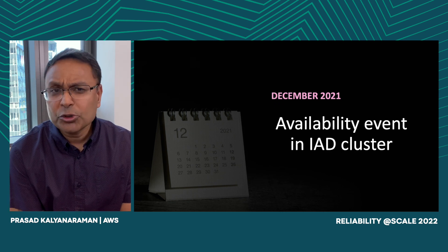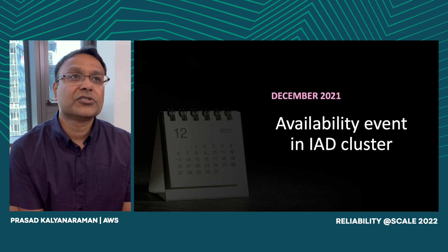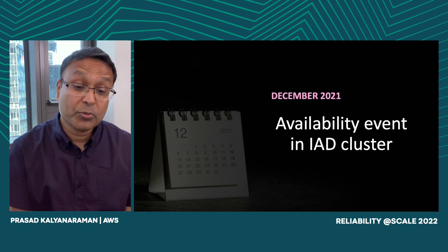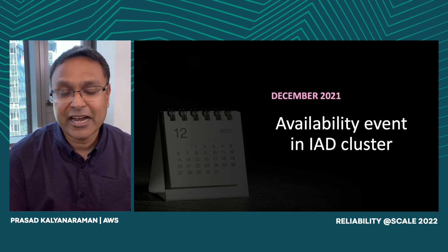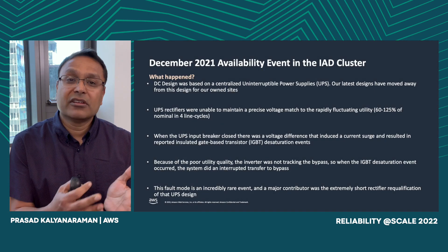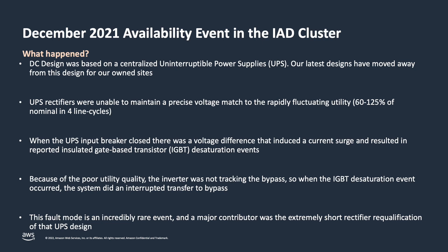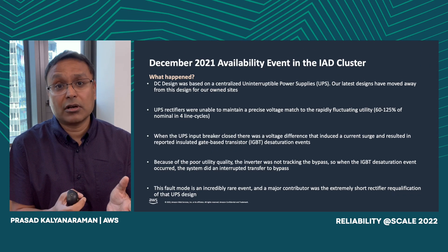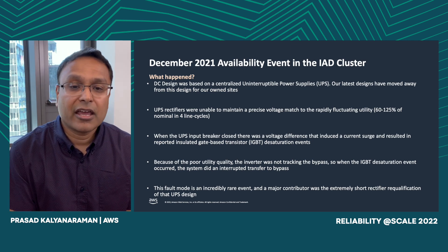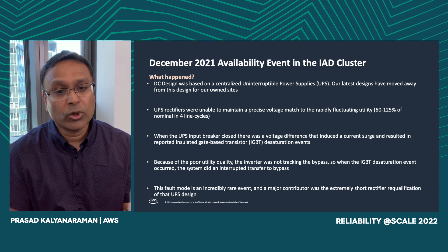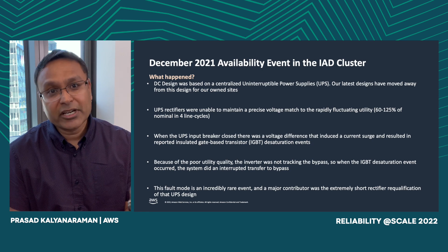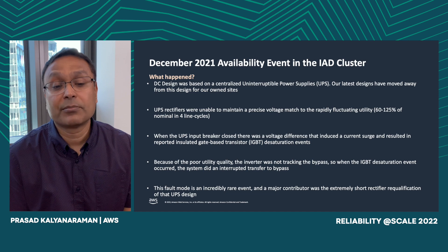I'm going to talk about a fairly unusual event that happened in Virginia in December — December 22nd specifically. It was so unusual that we worked with multiple UPS manufacturers to try to solve for it. In one of our Virginia data centers, we had a design based on a centralized UPS — our latest designs have moved away from that. What happened was the UPS rectifiers were unable to maintain precise voltage match with the utility, which was fluctuating very frequently, so the rectifiers couldn't maintain that precise voltage match.